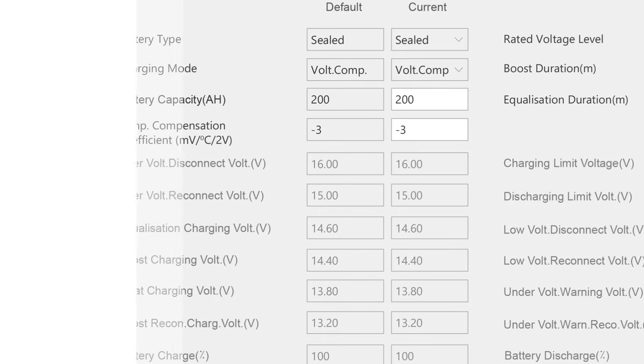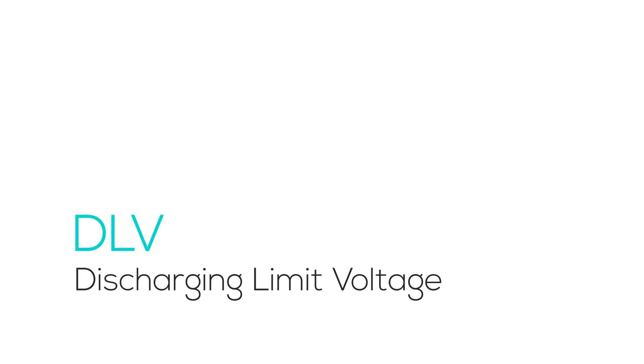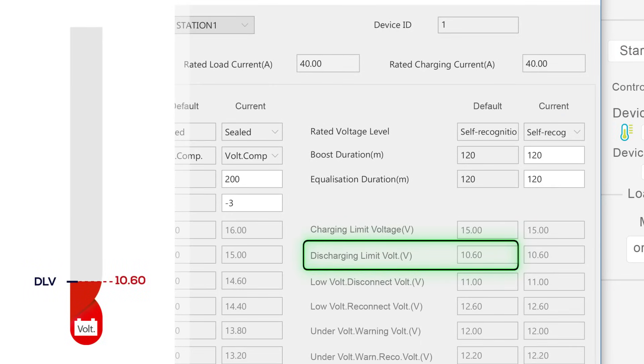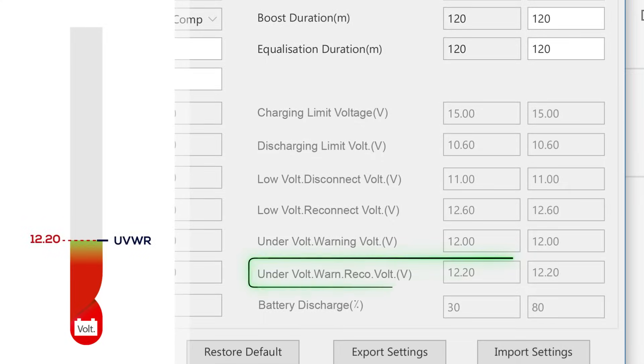LVD acts as a protective cutoff, disconnecting the load to prevent the battery from discharging to dangerously low levels that could cause permanent damage. In the discharging phase, DLV is the lowest discharge voltage with temperature compensation. When the temperature is high, the low voltage protection voltage is too low, and when the temperature is low, the DLV protection voltage is too high. UVWR marks the point of recovery, where the undervoltage warning clears, indicating the battery has regained enough charge to exit the danger zone.